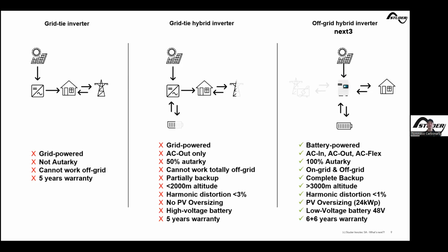Another difference: if you discharge your battery and the next day the solar comes back, with a grid-tied hybrid inverter you cannot charge your battery again, because the solar MPPT charger works with the grid as reference. So really be aware of which inverter you want to install in your system, because not every inverter is the same - you need to really determine which is the right inverter for you.